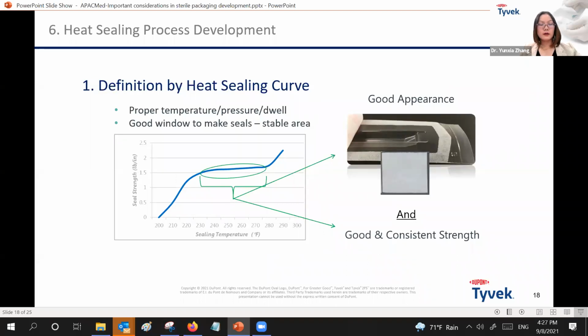So for the heat sealing process development, this is also very, very critical. The objective is to define an operating or sealing window with validated minimum, nominal, and maximum sealing conditions. This not only results in a heat sealing process that consistently produces acceptable seals, but also can optimize energy output, operational throughput, and efficiencies. So there are normally two ways recommended to optimize the heat sealing process. One is the evaluation of heat seal curves, and the other one is to use tools such as design of experiments using Minitab software. It really depends on the complexity of the process and the parameters.